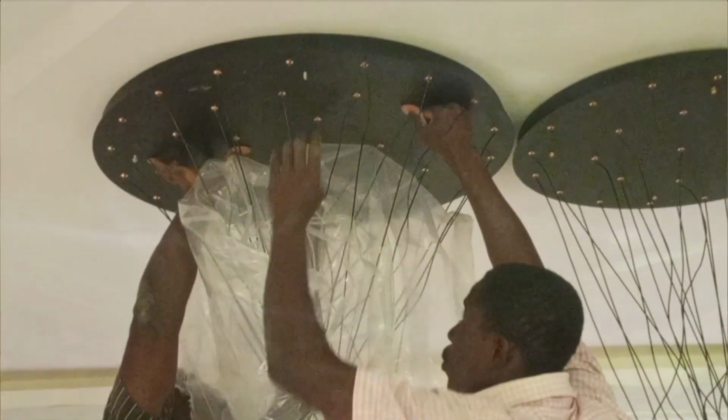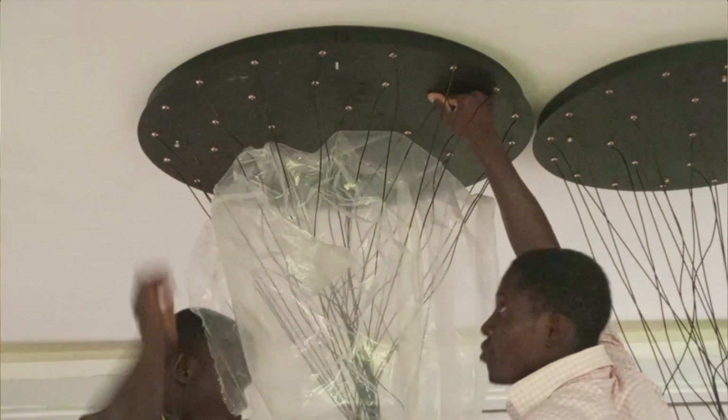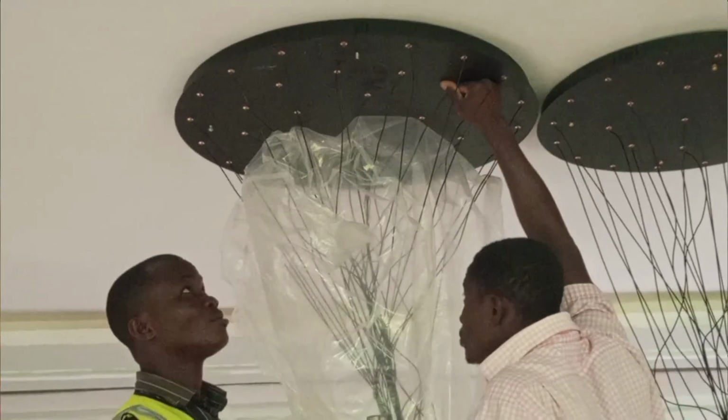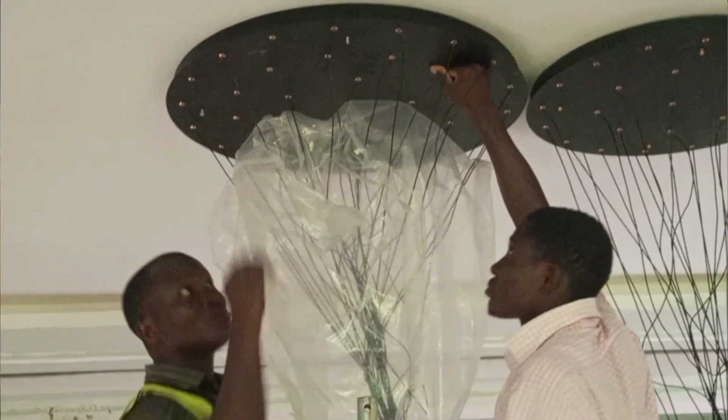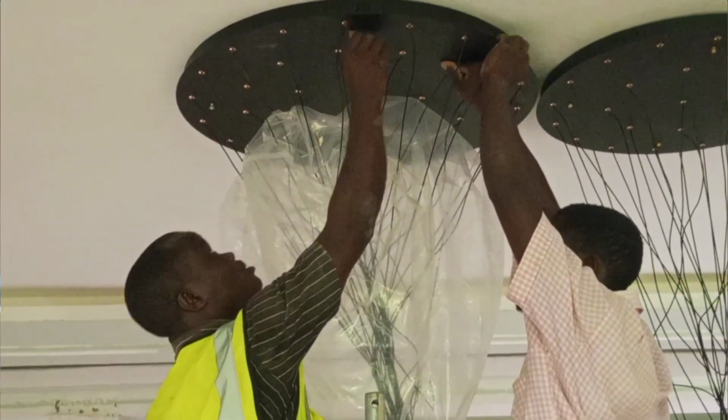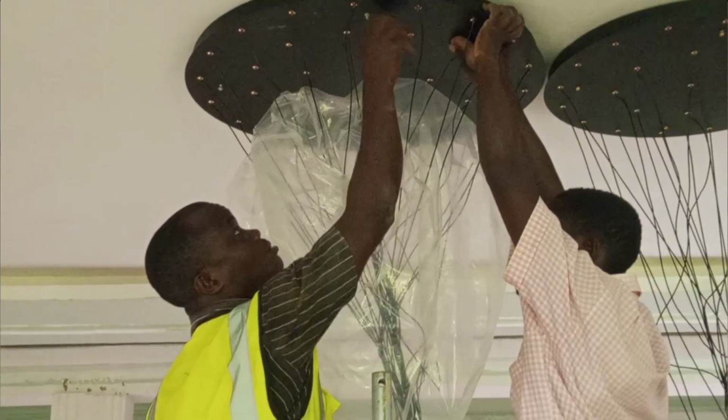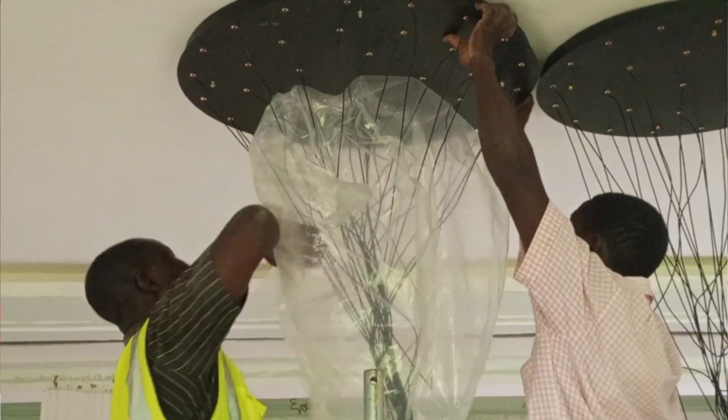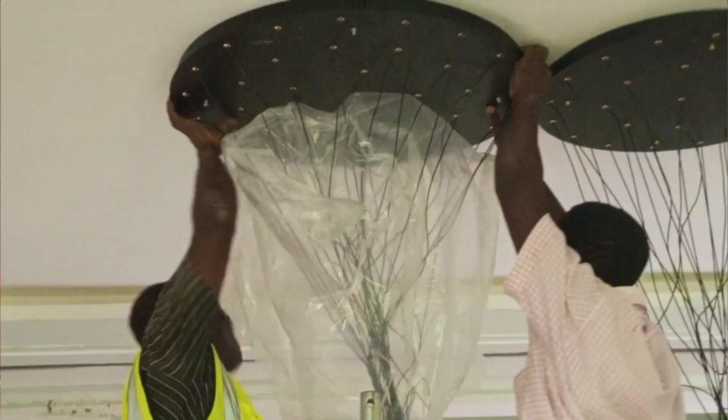Okay, so how do we go about this? How many circuits do we put this in? Do we put them together in one circuit and protect them with which breaker? Or we separate them and protect them with which breaker? All right, so if you are watching this and you are already an electrician, it is general knowledge that lighting circuits are protected with either 6 amps or maximum 10 amps.